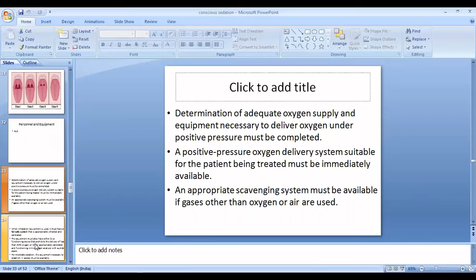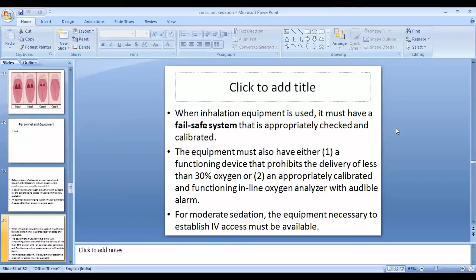Whenever inhalation equipment is used, a fail-safe system should be available that should be appropriately checked and calibrated. The fail-safe system means that whenever an equipment fails to deliver oxygen, another equipment should deliver the oxygen to the patient. The equipment must also have either a functioning device that prohibits the delivery of less than 30% oxygen, or an appropriately calibrated and functioning in-line oxygen analyzer with audible alarm. For moderate sedation, the equipment necessary to establish IV access must be available.